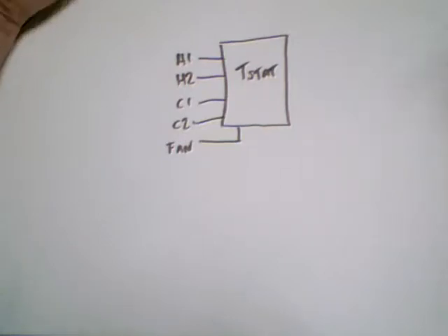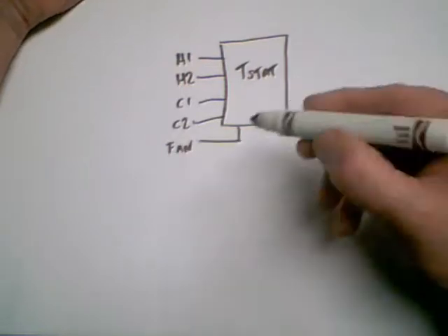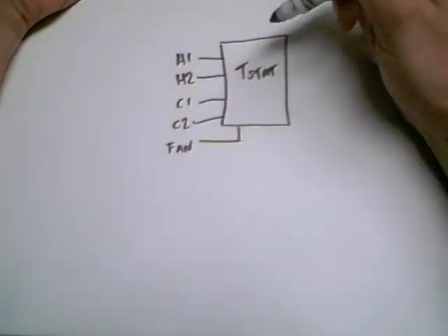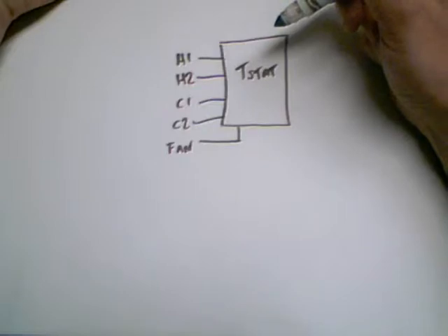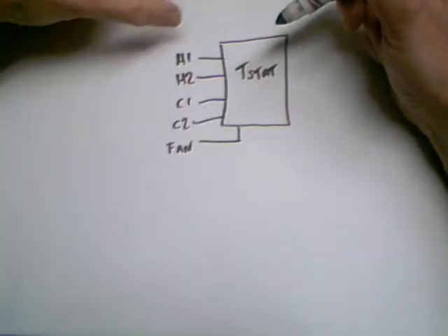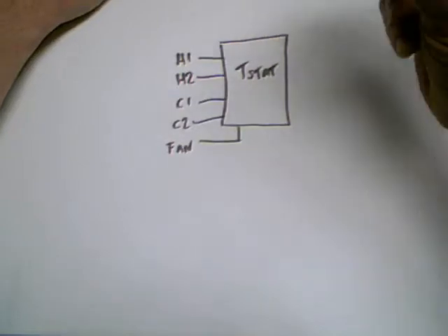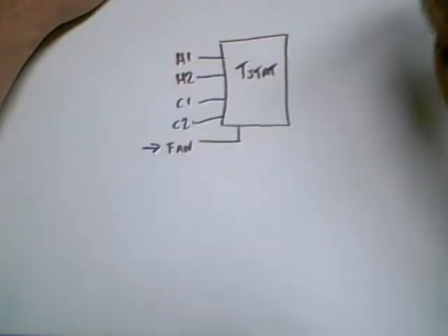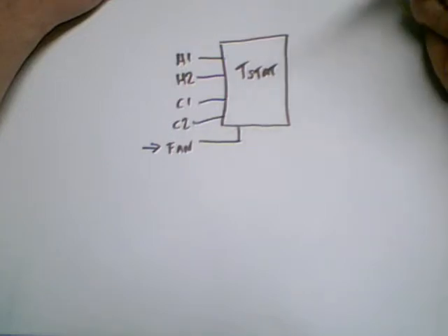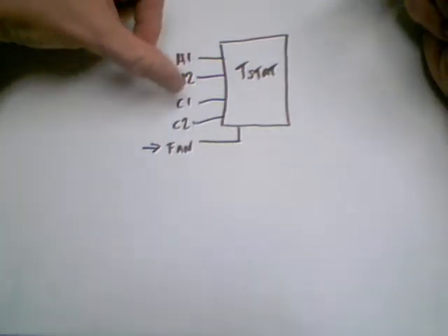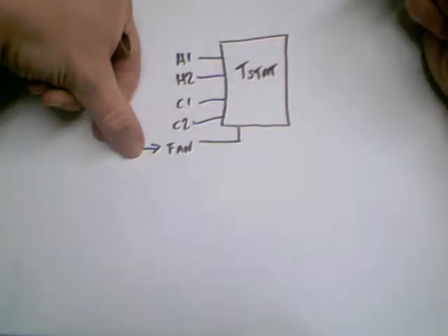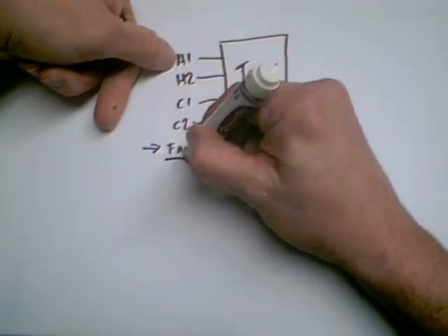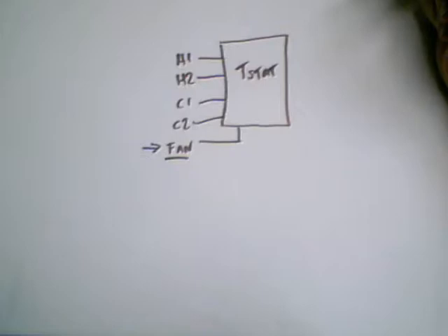So the way to think of that is when the fan is on, we're circulating fresh air into the building. When the fan is off, we're not. And that is independent of these modes here. So you can have the fan on without the heat or cooling if we're in occupied mode, like we've discussed in a previous video. Naturally, if it goes into heat or cooling mode, the fan comes on itself, but that is not to be confused with having this particular line chosen, which is a switch inside of the thermostat, because that turns the fan on for recirculation, but it does not turn on the dampers that actually bring in outside air. So this is a little bit misleading, because it's not just a fan, but it's really the outside air damper that gets opened.